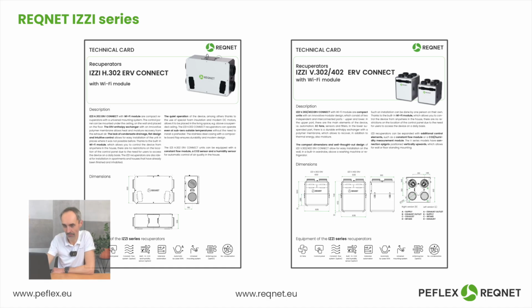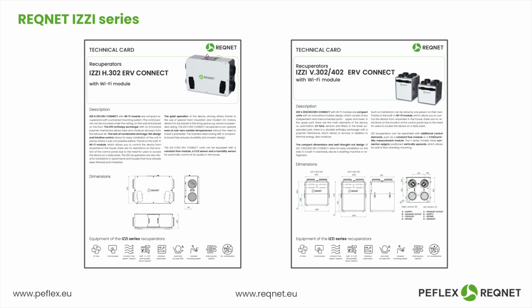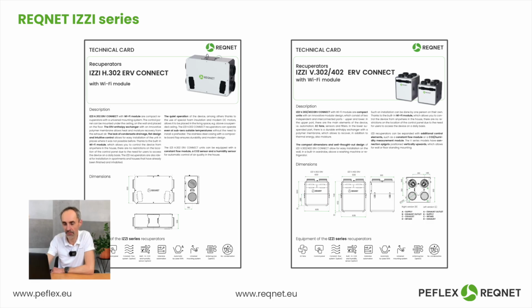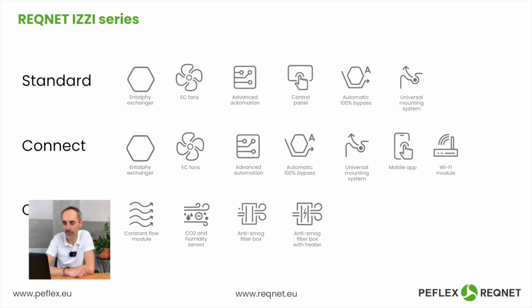Our IZZI series recuperators come in two construction versions, the H version, which has horizontal connectors, and the V version with vertical connectors. As for the V version, we also have two capacities available, 300 cubic meters and 400 cubic meters. And right now, we also have different control options available, because we have our IZZI standard recuperators, which are controlled via a wall-mounted control panel, and we have our IZZI Connect series, which are controlled through an app installed on a mobile device or phone, which communicates with the ventilation unit via Wi-Fi. When it comes to functionality, both the standard and the Connect control exactly the same functions in exactly the same way.